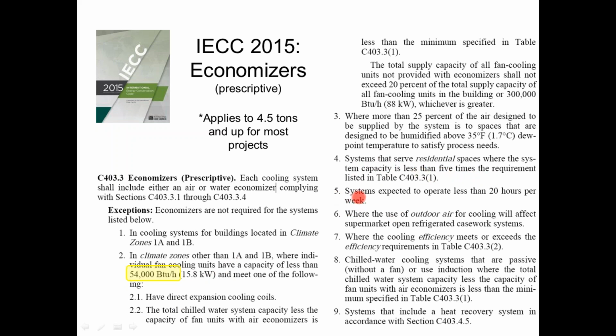If my system's only going to operate on Sunday morning for 2 hours, then I wouldn't necessarily have to put an economizer in if I wasn't using the space for anything else really. Supermarkets, and there's a few things like that where there's some exceptions. If I have heat recovery systems, if I have chilled beams, those kind of things might not have to do it. But for a rooftop job, I'm probably going to have to do it. As soon as I get basically 5 tons and up, I'm going to have to do it. It's kind of a good check figure in your head.